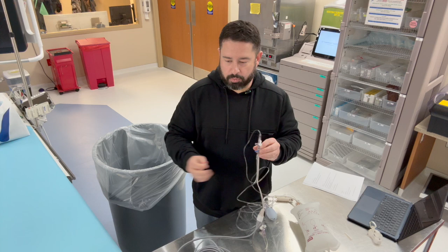So I'm going to flip this up and off to the patient so that the tail is always going down. I think of it like the tail of a dog just hanging down. This is a tail. I always have it going down. I flip my transducer up, which is going to the patient. This is a vented cap. If it's not a vented cap, you have to take it off. You must take your cap off so that this port is open to atmospheric air.